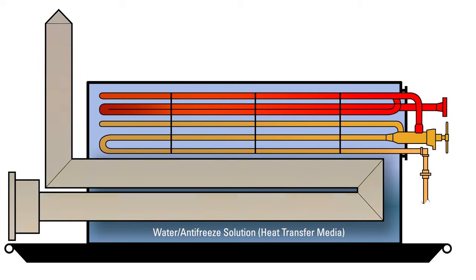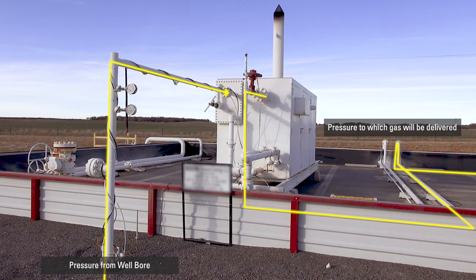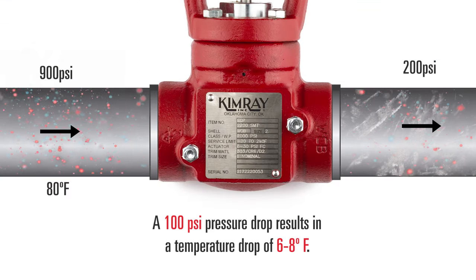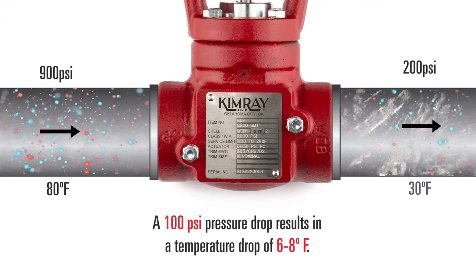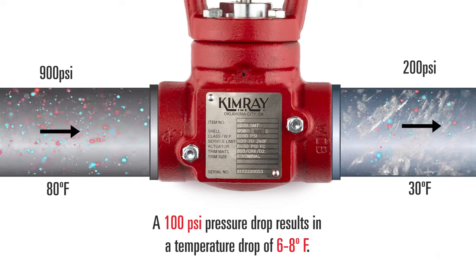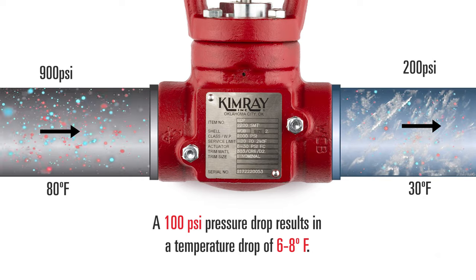All of these components are needed because the pressure of the well bore is higher than that of the pipeline to which the gas is being delivered. When you have a pressure drop, you have a temperature drop as well. With that temperature drop, freezing can occur or hydrates will form, and both of those issues can cause problems for the producer.